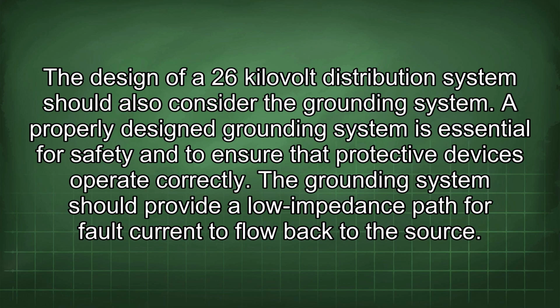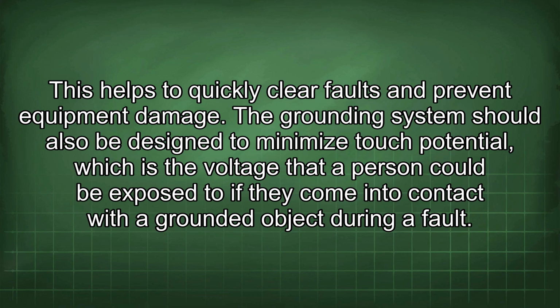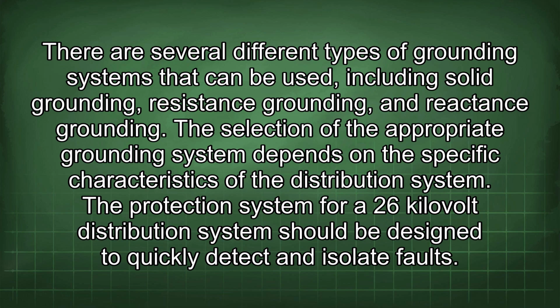A properly designed grounding system is essential for safety and to ensure that protective devices operate correctly. The grounding system should provide a lower impedance path for fault current to flow back to the source. This helps to quickly clear faults and prevent equipment damage. The grounding system should also be designed to minimize touch potential, which is the voltage that a person could be exposed to if they come into contact with a grounded object during a fault. There are several different types of grounding systems that can be used, including solid grounding, resistance grounding, and reactance grounding. The selection of the appropriate grounding system depends on the specific characteristics of the distribution system.